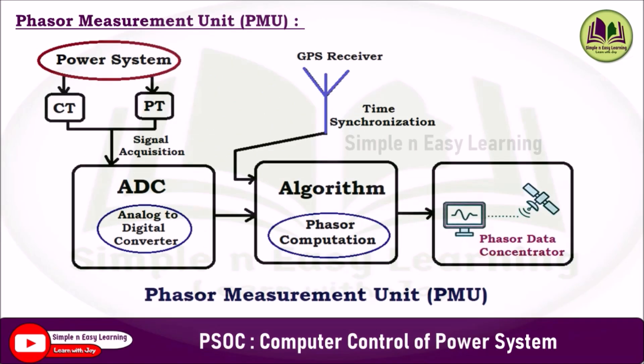This is a complete block diagram of a phasor measurement unit in a power system. You will have a measurement unit with CT and PT to measure current and voltage, followed by signal acquisition and an ADC. There is an algorithm for phasor computation, and for that we need time synchronization through a GPS receiver. The output is then given to the phasor data concentrator.